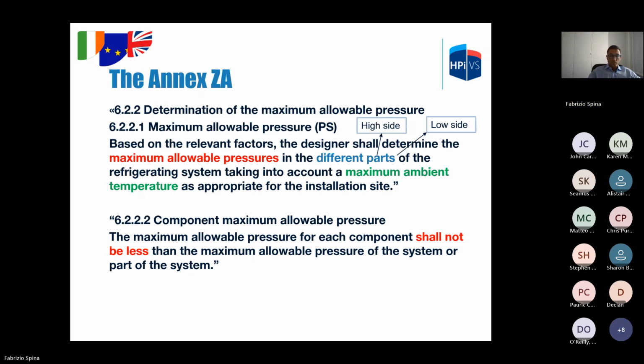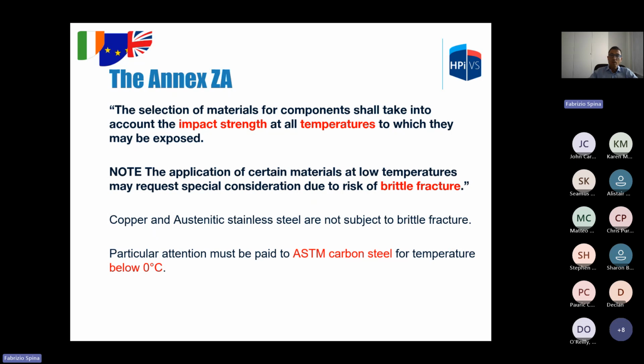The component maximum allowable pressure shall not be less than the maximum allowable pressure of the system or part of the system. It is the same that we saw before about the integration of the system within the global conformity assessment. The selection of material for components shall take into account the impact strength at all temperatures to which they may be exposed. The application of certain materials at low temperatures may require special consideration due to risk of brittle fracture. This is a very important point.